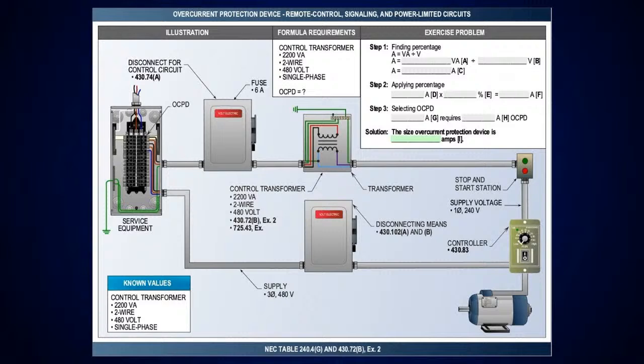But I'll point out again, you're going to notice there's no superscript 1. Now, if I'm over 9 amps, then you take it at 125%, and guess what's there? A superscript 1, which means I go up to the next standard size.